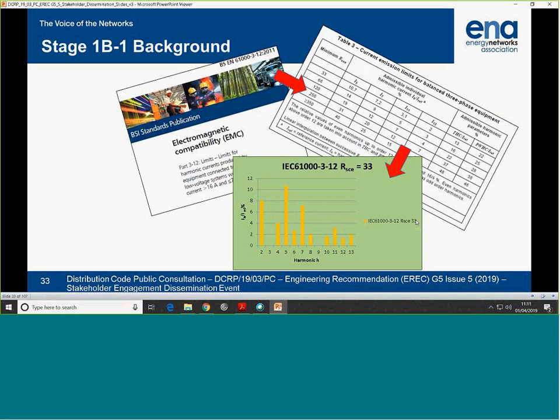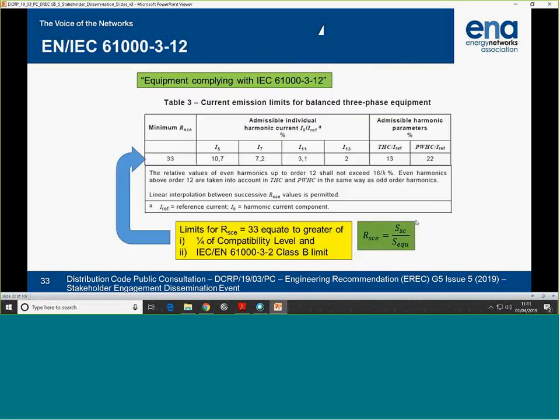So that's one aspect. And if we look at that row in particular, and when the manufacturer complies with these limits, so look, we've got the fifth harmonic at 10.7%, meets each of these limits, they can say it complies with 61312. If they exceed any of the limits, there's the other part of the tables. I'll go on to that. Where do these limits come from? What do these limits mean?